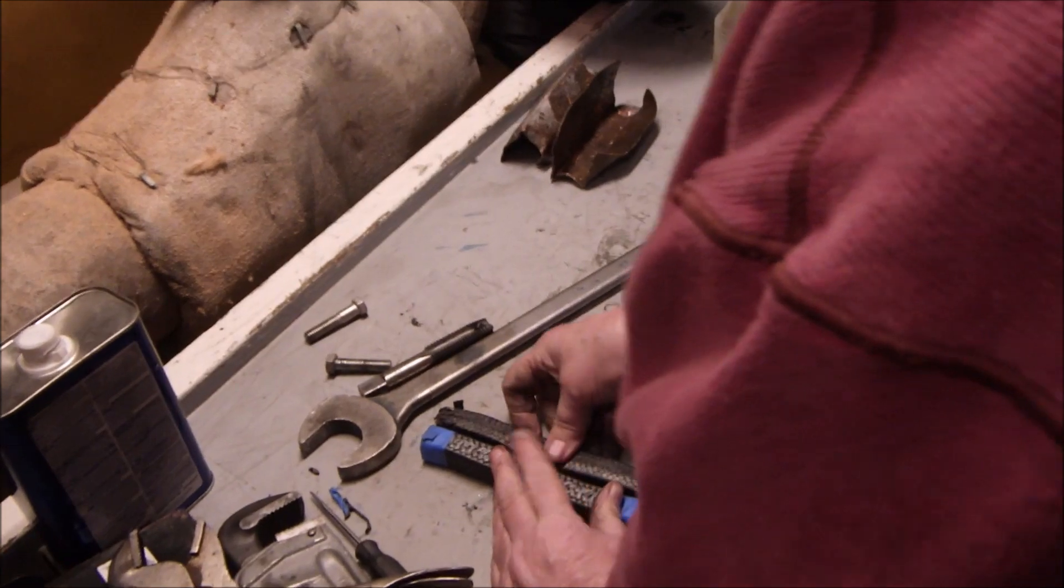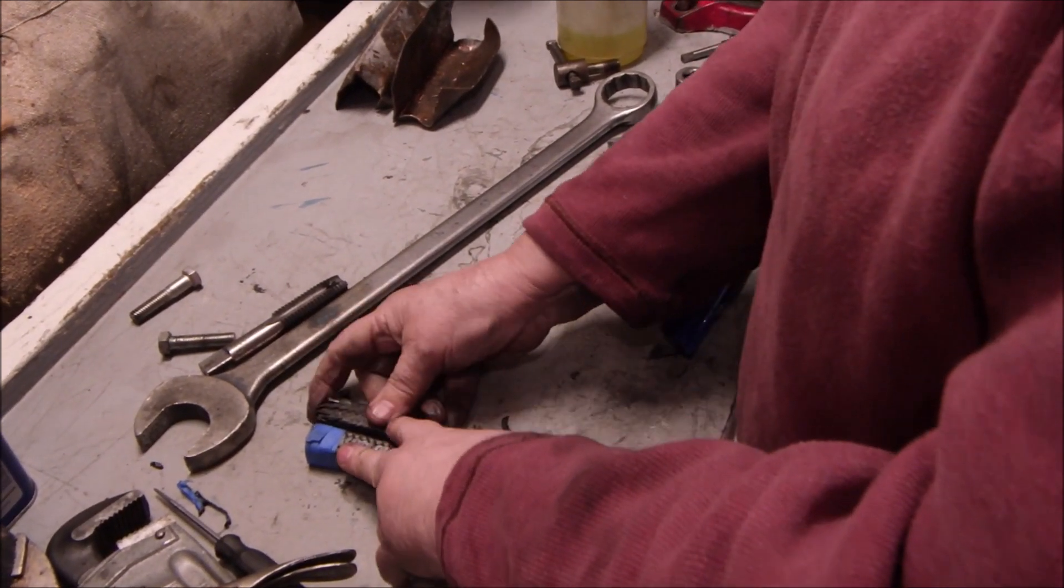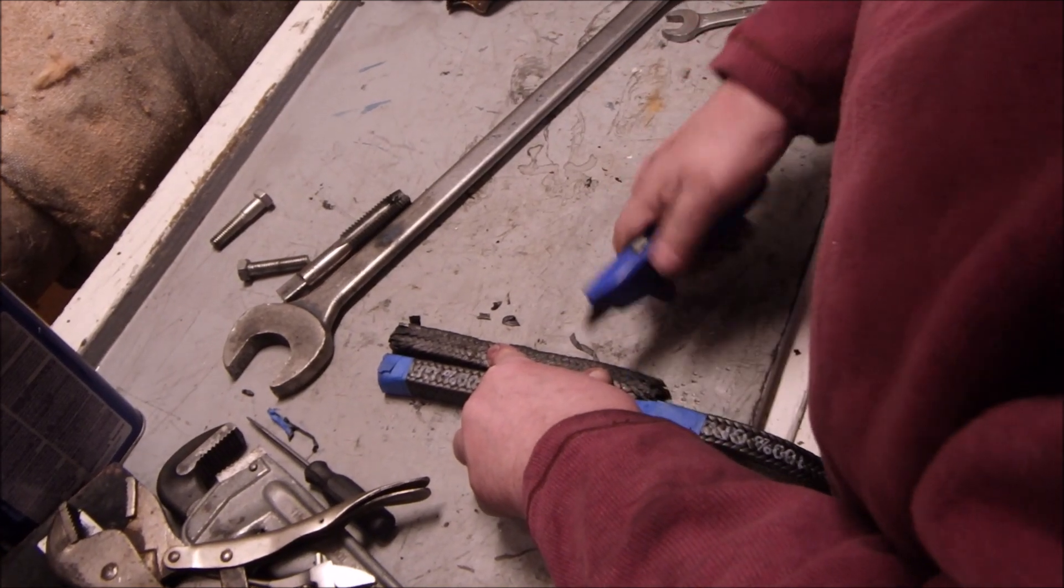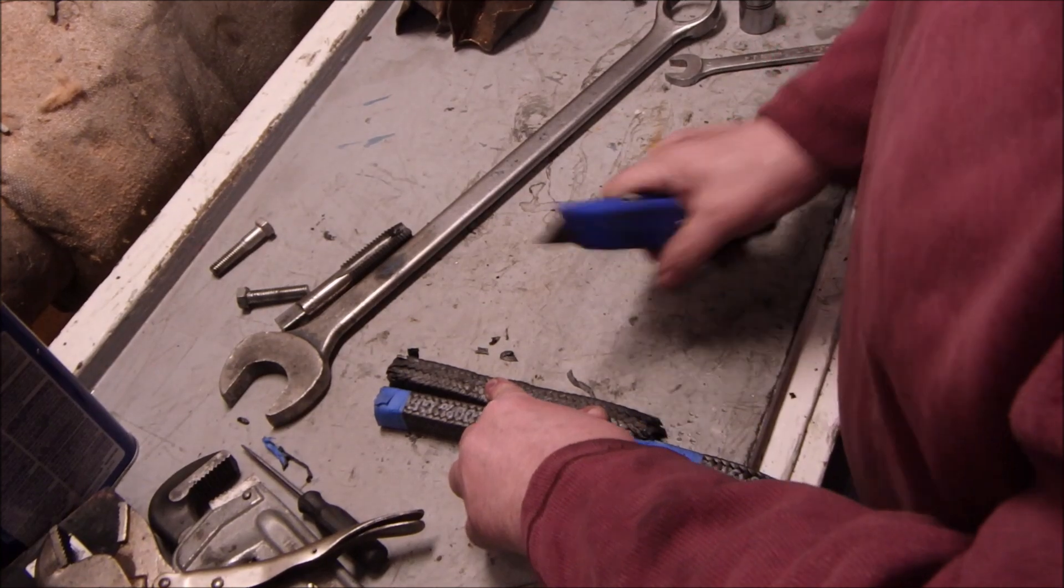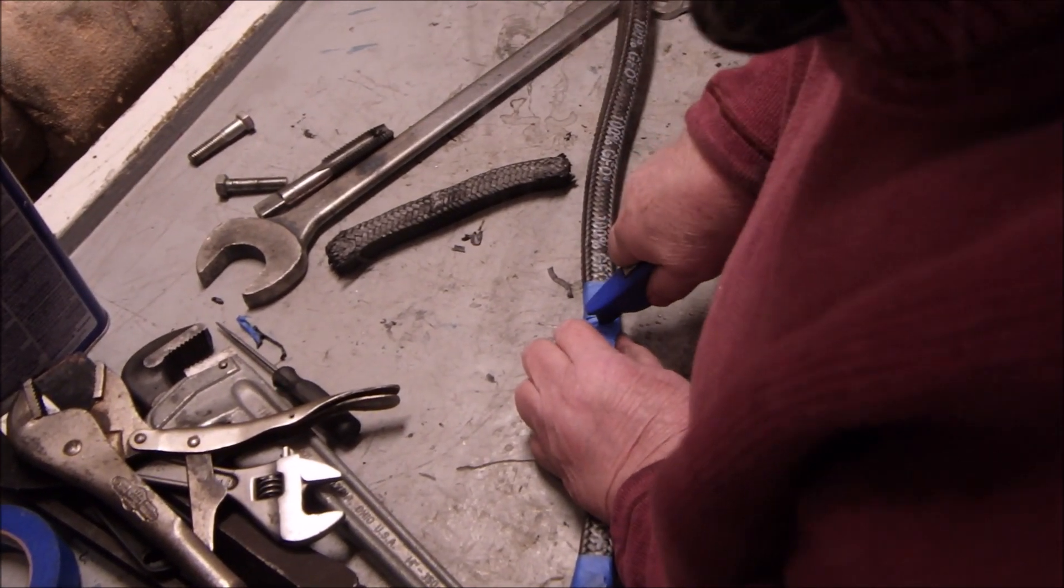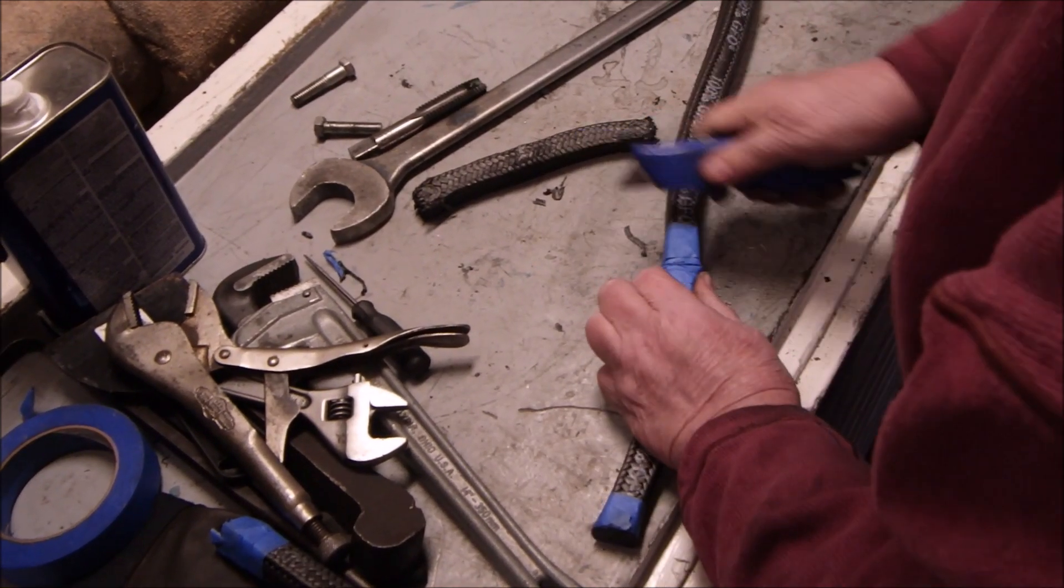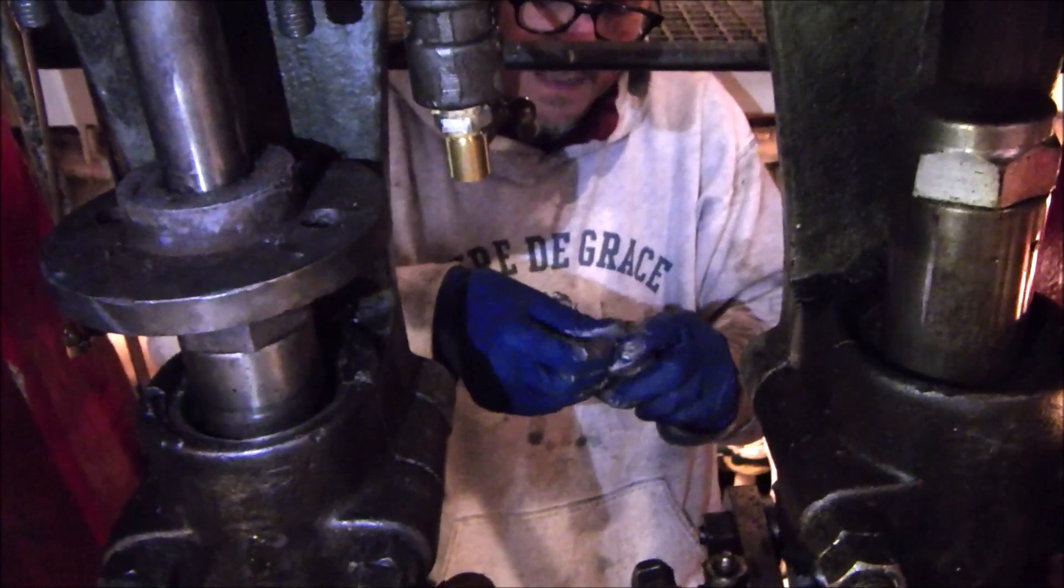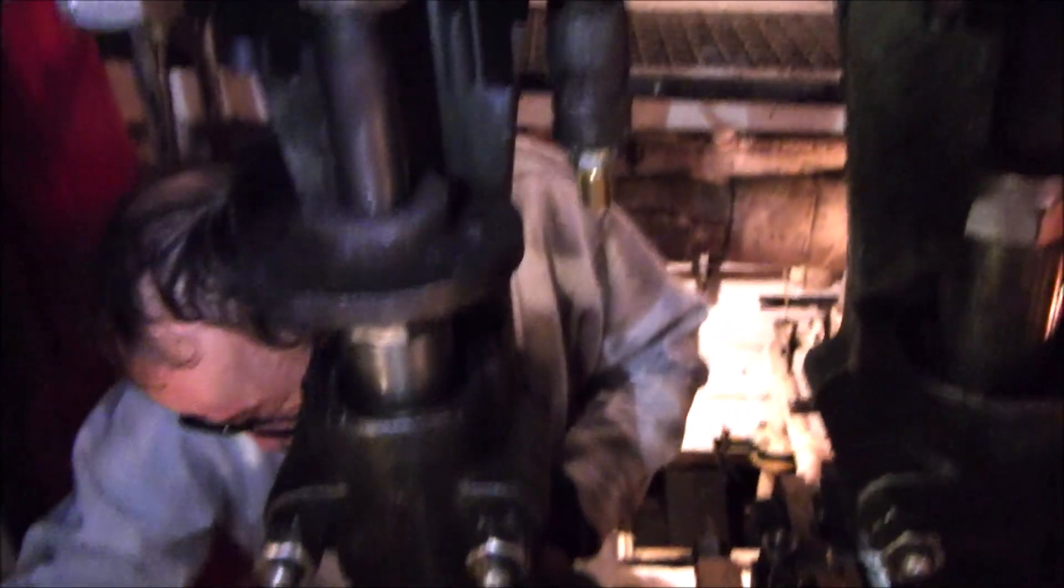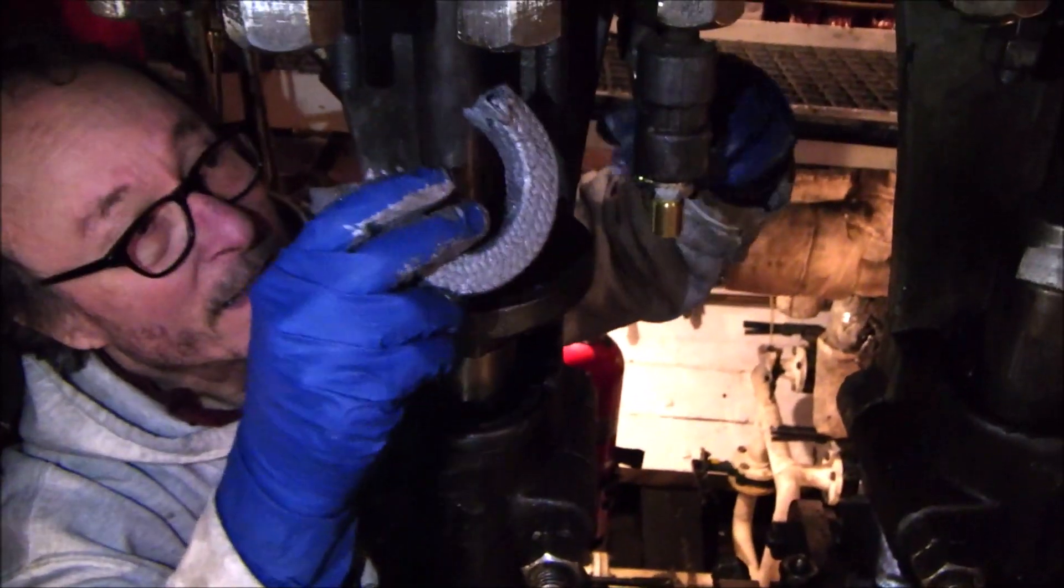With the engine taken care of, we do have some other tests today. So one of the last things to do with the valves is going to be repacking them. The packing is the seal that keeps steam from leaking out around the valve rod. Our packing here is sort of a braided fiber with graphite. So we cut them all to the right size and then these get wrapped around the valve rod or piston rod. And sometimes there might be 10 stacks of these rings up in there. They just get very carefully packed up in around the rod and squashed into place.